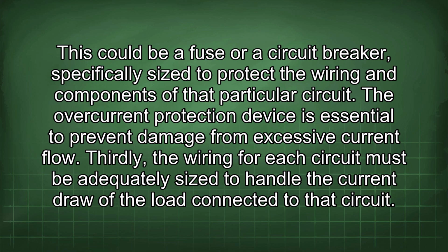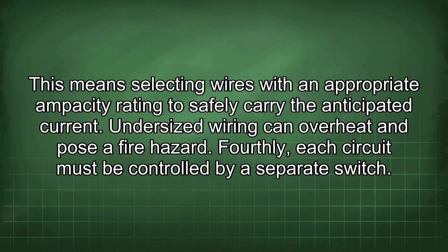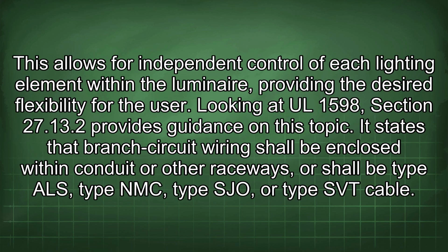Thirdly, the wiring for each circuit must be adequately sized to handle the current draw of the load connected to this circuit. This means selecting wires with an appropriate ampacity rating to safely carry the anticipated current. Undersized wiring can overheat and pose a fire hazard. Fourthly, each circuit must be controlled by a separate switch. This allows for independent control of each lighting element within the luminaire, providing the desired flexibility for the user.